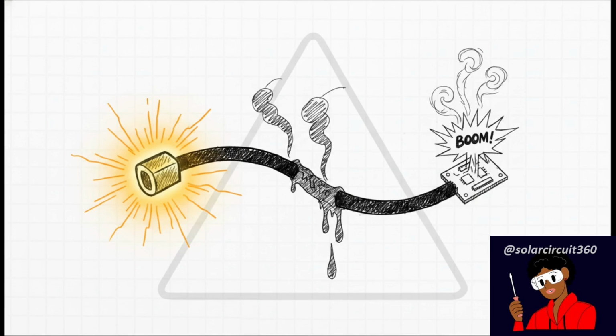A lot of folks just pick the highest number in the BMS app because they want maximum power. But listen, if your BMS current limits don't match the true safe ampacity, the safe current carrying capacity of your cables, your bus bars, and the internal electronic switches inside the BMS, known as MOSFETs, you are asking for trouble. You risk melting cables, getting dangerously hot terminals, and literally frying your hardware. Your settings have to absolutely respect the physical hardware limits.